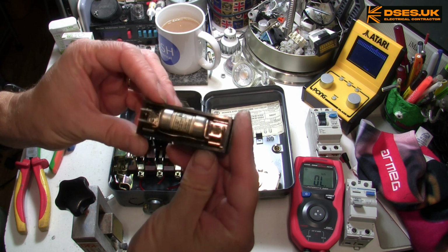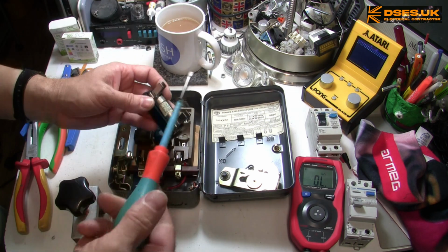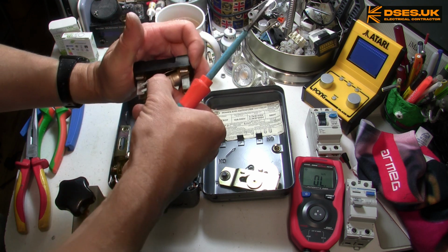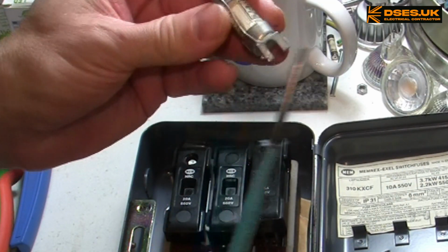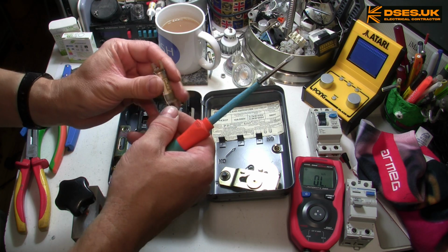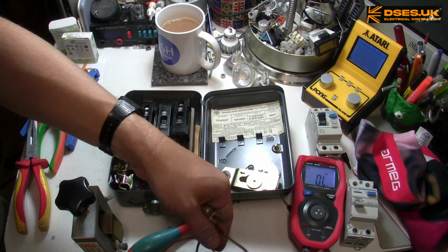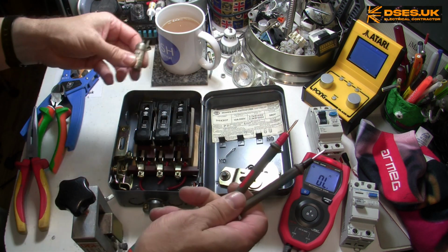Yeah, boy, can you see that? This is what we picked up on our EICR, and I need to get this out with my old Hager pokey screwdriver, which is why its insulation is so knackered. Let's have this out. Yeah, how long do you reckon it's been like that? Well, they had this actually on a 32 amp circuit, supplying some milling machine. Obviously these are 10 amp fuses. Let's just go back to my little TIS here. Oh, that fuse actually works.